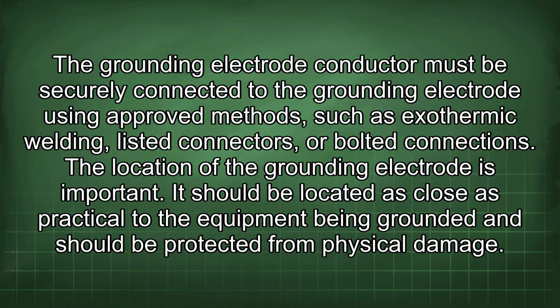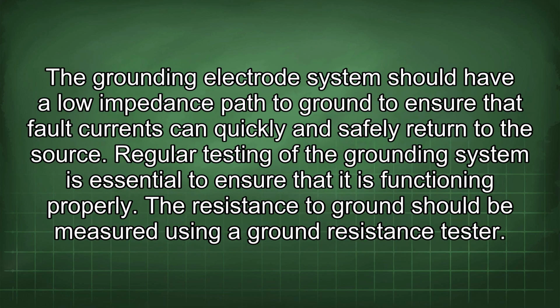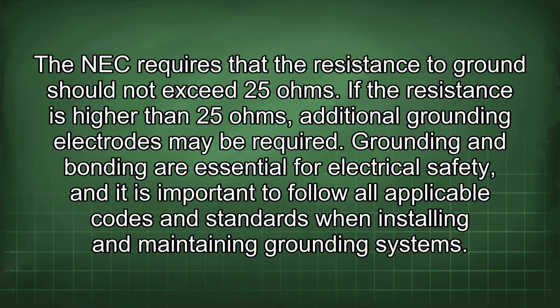The location of the grounding electrode is important. It should be located as close as practical to the equipment being grounded and should be protected from physical damage. The grounding electrode system should have a low impedance path to ground to ensure that fault currents can quickly and safely return to the source. Regular testing of the grounding system is essential to ensure that it is functioning properly. The resistance to ground should be measured using a ground resistance tester. The NEC requires that the resistance to ground should not exceed 25 ohms. If the resistance is higher than 25 ohms, additional grounding electrodes may be required.